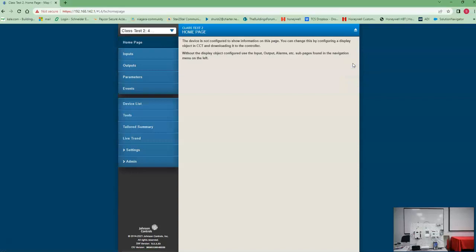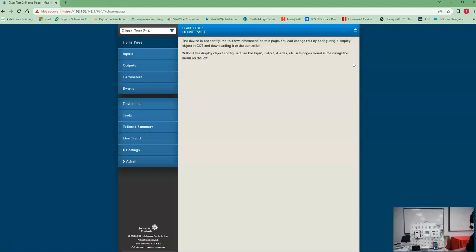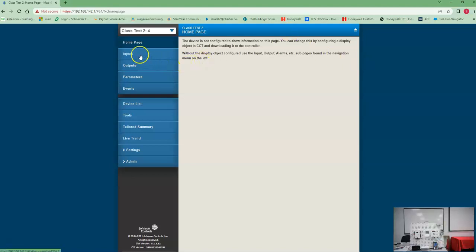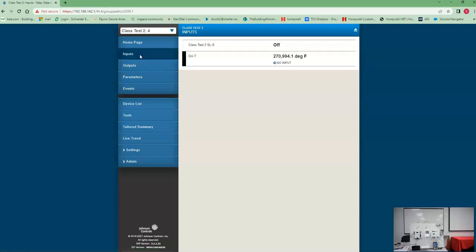This will say that this screen doesn't have any display items on there. That's okay. Inside CCT at the bottom, there's a little display tab where you have the option of creating display points, which I highly recommend, but that's another thing. The Map Gateway doesn't care if there's no display. We can still see all the points in the controller. So we come over here to inputs, and there's my inputs. I got a discharge air temp input right here. Outputs, there's my outputs.